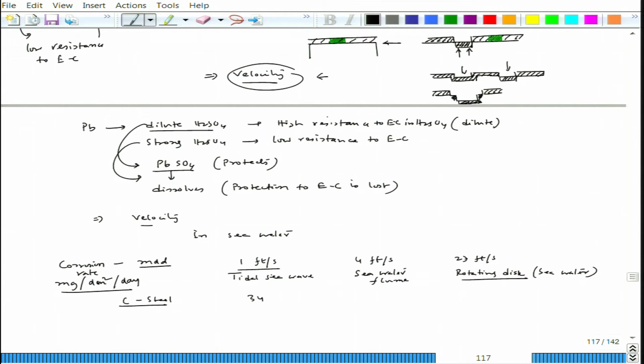This is 34 in a medium moving at a speed of 1 feet per second for carbon steel. Then it is 72 when the speed becomes 4 feet per second, and it becomes 254 when it is 27 feet per second. So, this is the kind of increase in corrosion rate observed with the increase in speed, and you could see that up to 4 feet per second there is not much increase, but once it reaches 27 there is quite a lot of increase.